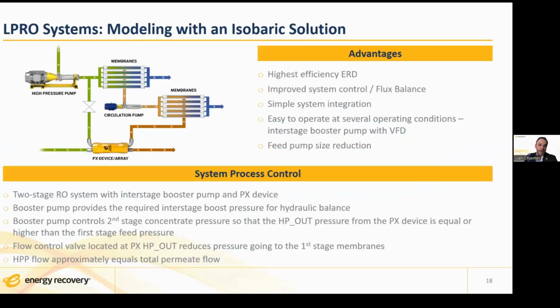If we then include the PX device, the energy recovery device, we have the two-stage system with interstage booster pump and the PX. The booster pump provides the required interstage boost and also covers the hydraulic losses in the system. It also controls the concentrate pressure, so that with the PX we can achieve the required pressure at the membrane feed in the first stage. In case this pressure is too high, we can set a pressure control valve at the high pressure outlet of the PX to reduce the pressure to the membrane feed and to control the production. And as commented, the high pressure pump flow has been reduced to just the permeate flow.